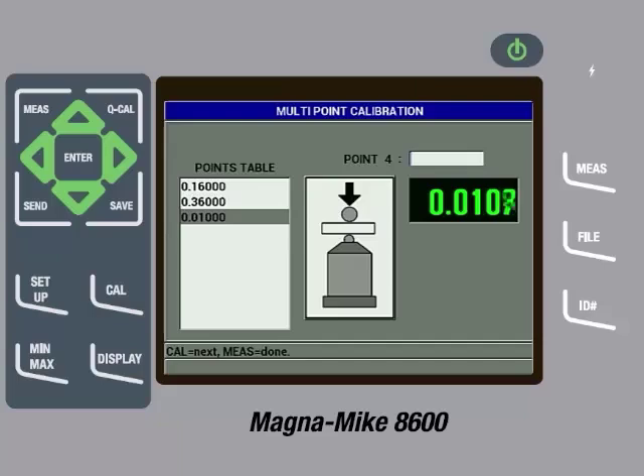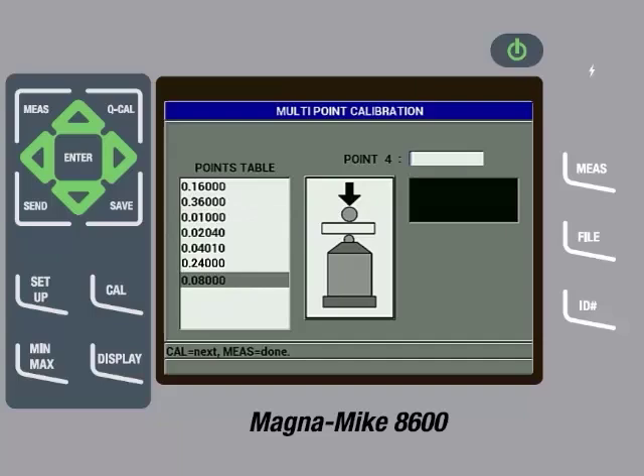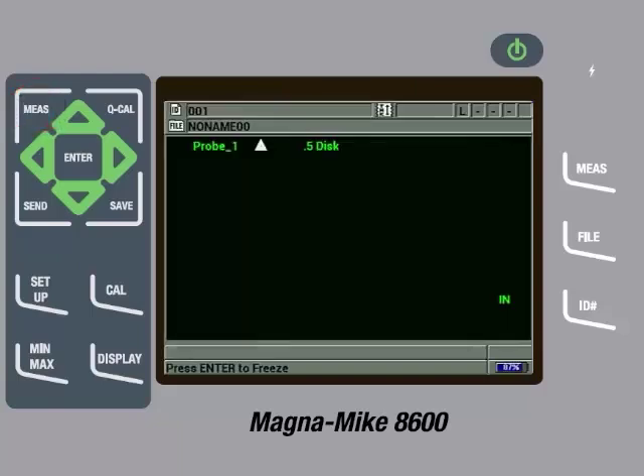We can then repeat this process for the other calibration standards until they are all added to the list of calibration points. Once they have all been entered, we can press the Measure key. We have now completed a full multi-point calibration. It is good practice to check a few of the reference standards after the calibration has been completed to make sure they are measuring within specification.